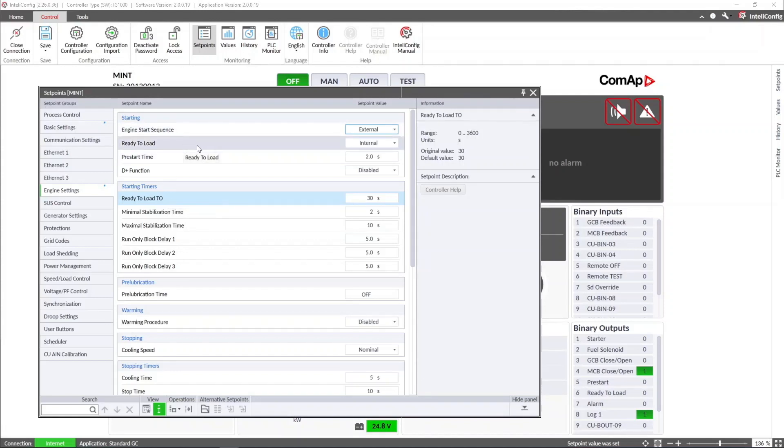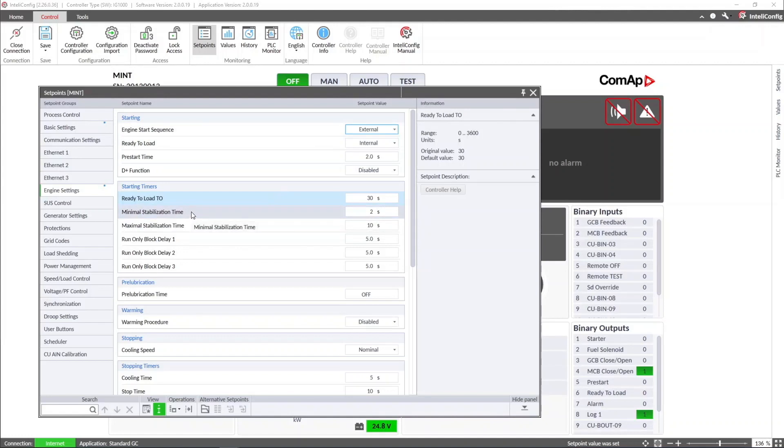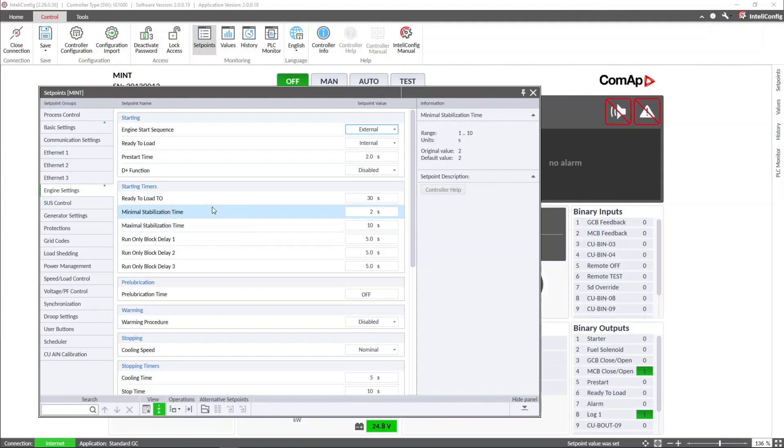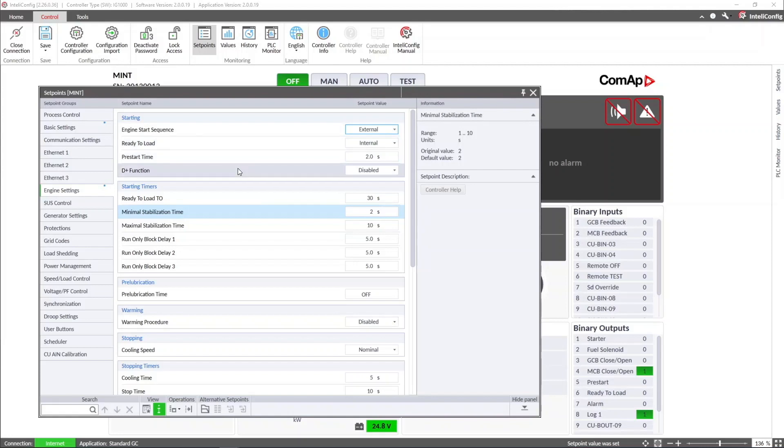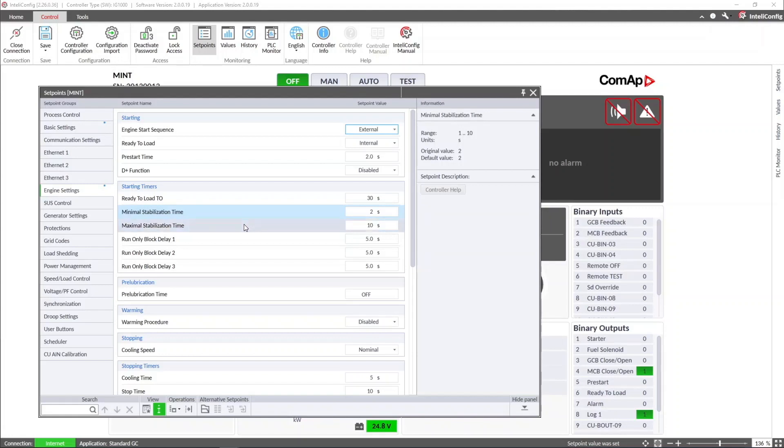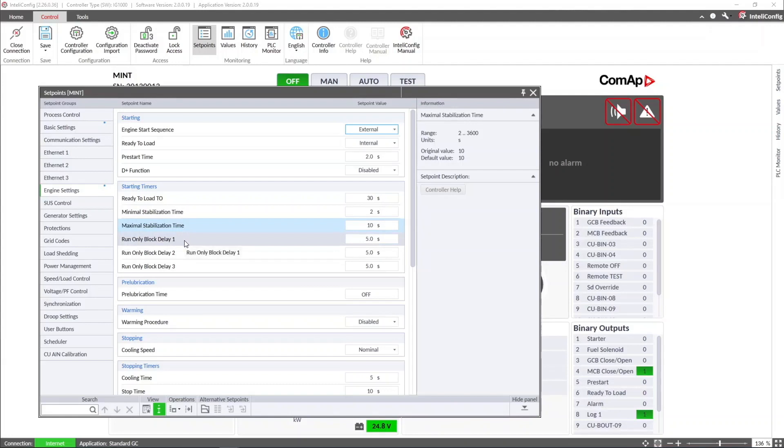The minimal stabilization time adds a delay for closing the generator circuit breaker after voltage and frequency conditions are within the defined limit. If voltage and frequency are out of the limits, the controller will wait the time configured in the maximal stabilization time before shutting down the genset.